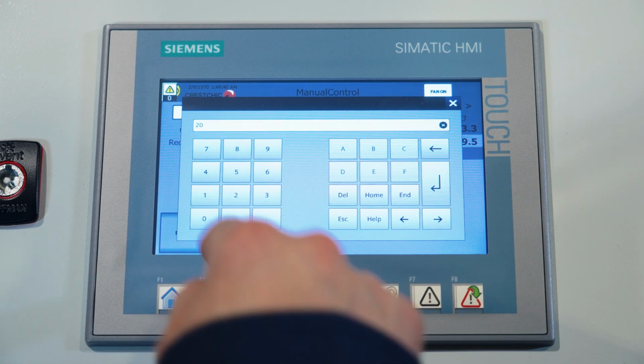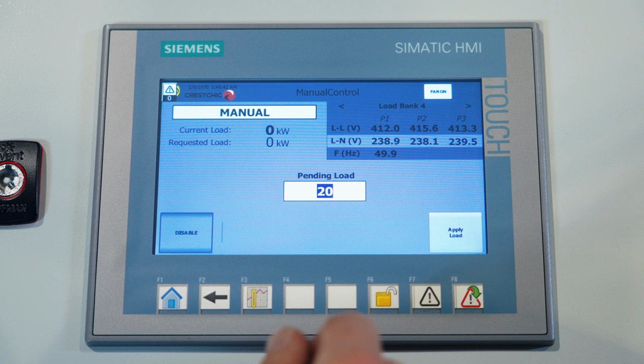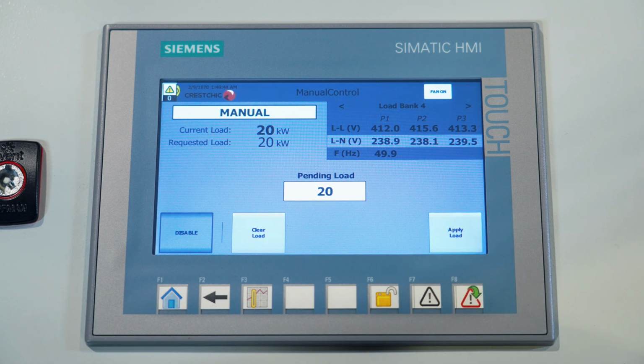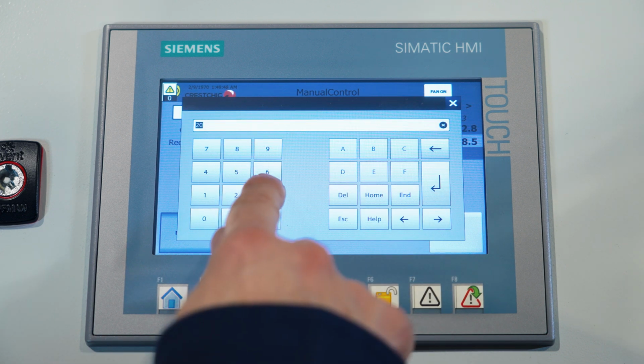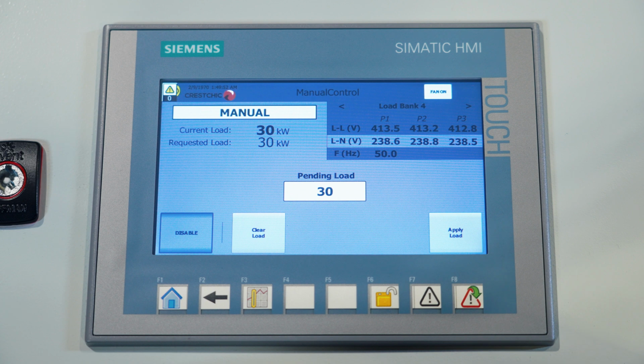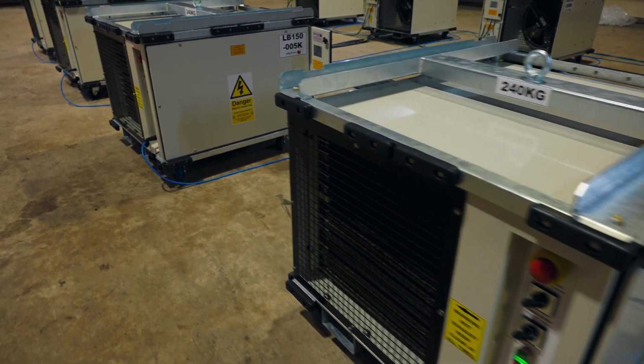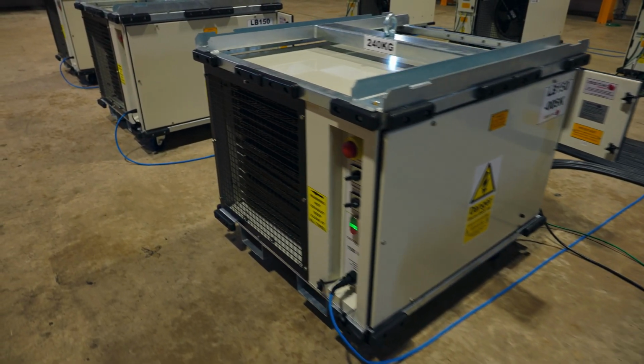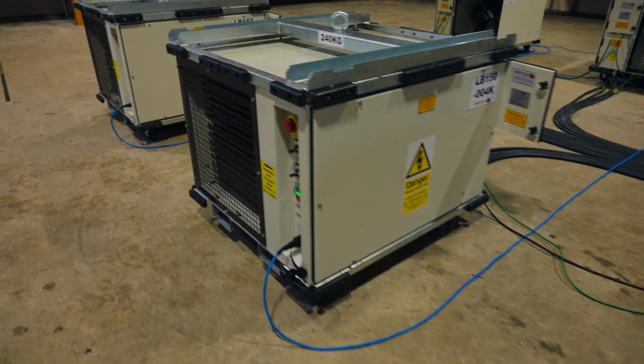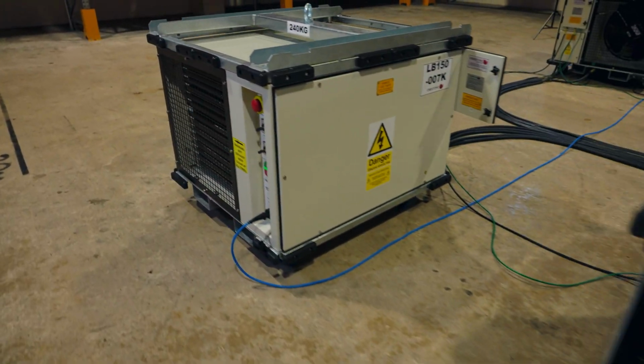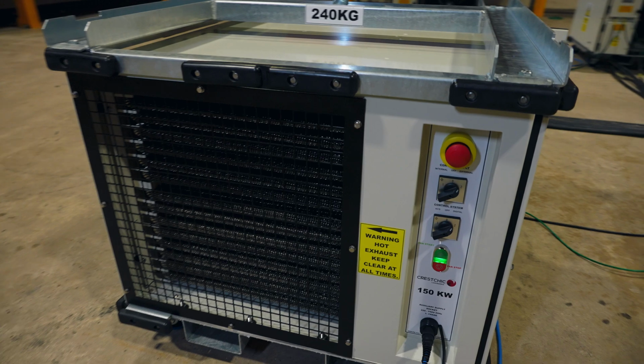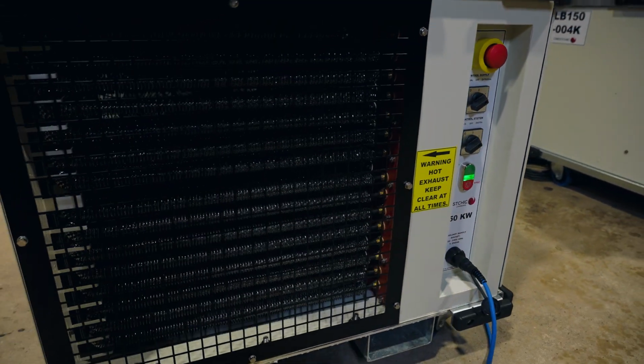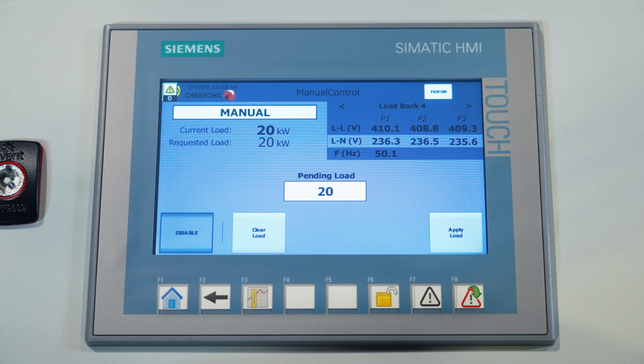The first method is manual control. This is similar to the KCS controller in that a value is set and then applied. When going into the manual mode, all load banks will start up at the same time to the stage of ready for load. It is possible to add an optional maximum step size in this mode, so when applying, for example, a load from 0 kilowatts to 100 kilowatts, a maximum load step size of 25 kilowatts can be set so that the load is ramped up in 25 kilowatt increments to achieve a requested load of 100 kilowatts.